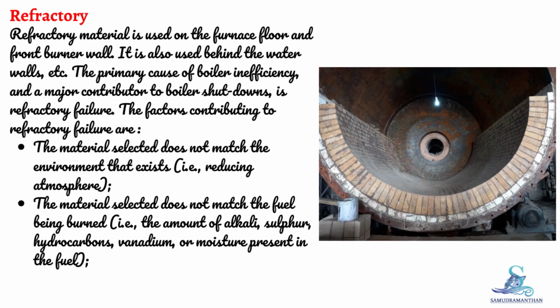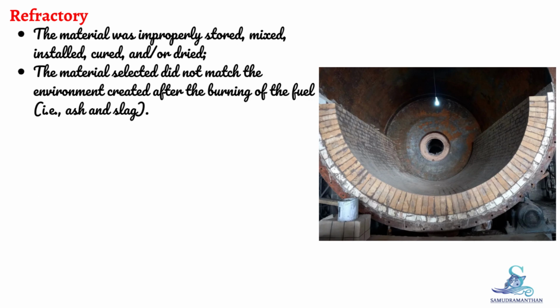The factors contributing to refractory failure are: the material selected does not match the environment that exists, that is, a reducing atmosphere. The material selected does not match the fuel being burned, that is, the amount of alkali, sulfur, hydrocarbons, vanadium, or moisture present in the fuel. The material was improperly stored, mixed, installed, cured, and/or dried. The material selected did not match the environment created after the burning of the fuel, that is, ash and slag.